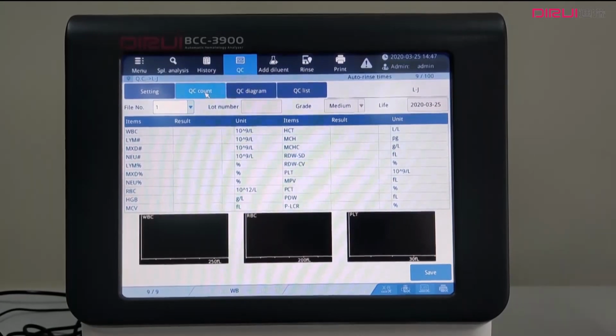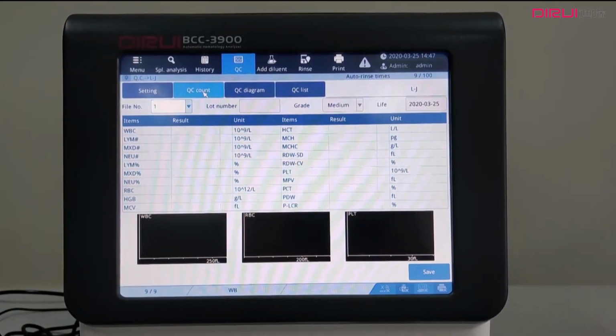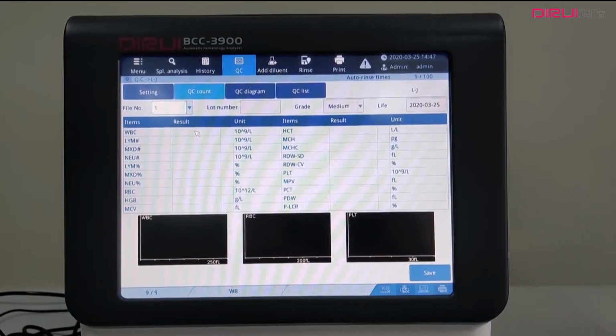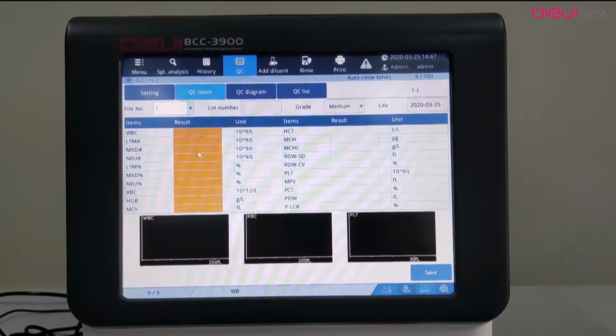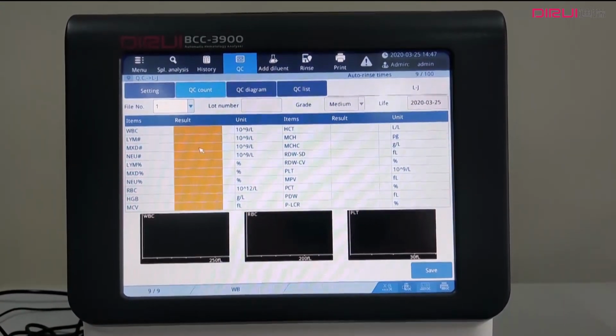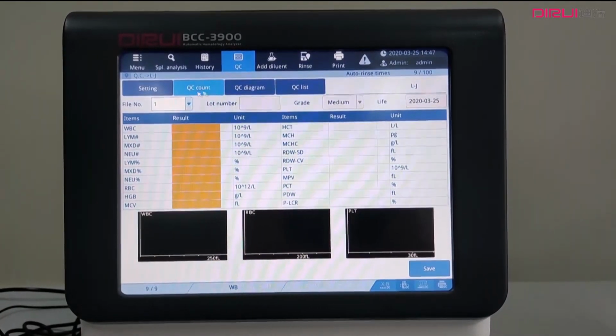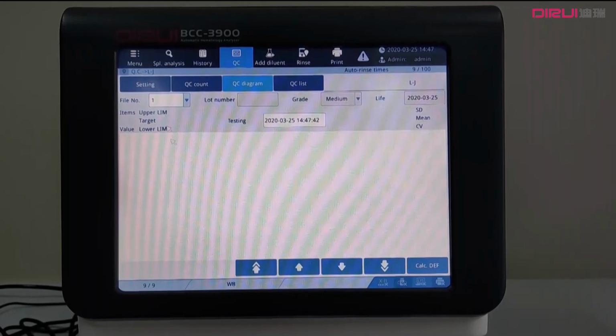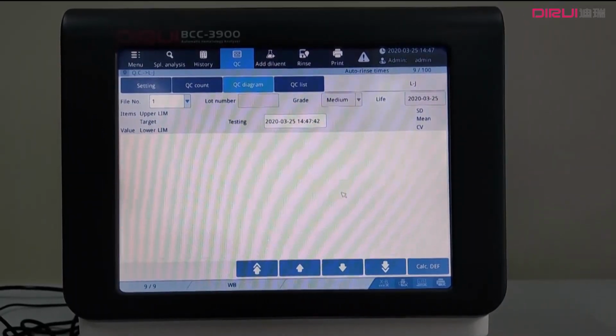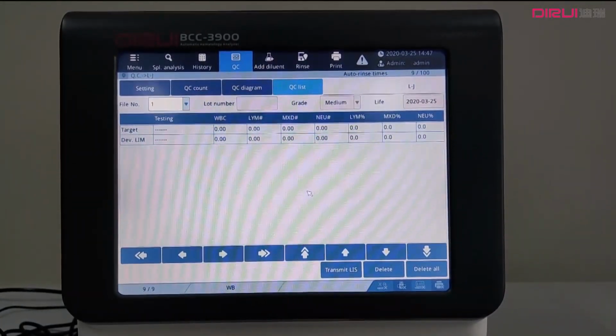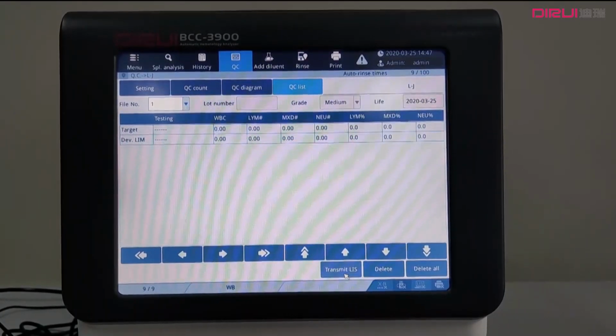This time you will conduct the QC. Press your QC here and then conduct your QC, and all of the results will be shown in the result column. If there is any abnormal information, it will be highlighted in red. Otherwise, if the QC is normal, it is shown in normal color. After this, you can check the QC diagram according to your selected choice. The QC diagram will be shown in this interface. After that, you can check the QC history from this menu, and you can send this information to LIS, or you can delete this information.